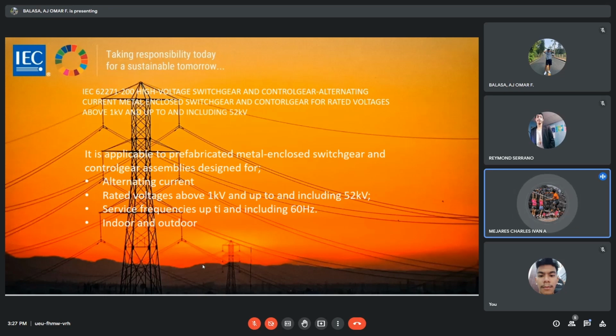IEC 62271-200: High voltage switchgear and control gear, alternating current metal enclosed switchgear and control gear for rated voltages above 1 kilovolt and up to and including 52 kilovolts. It is applicable to prefabricated metal enclosed switchgear and control gear assemblies designed for alternating current, rated voltages above 1 kilovolt and up to and including 52 kilovolts, service frequencies up to and including 60 Hz, indoor and outdoor installations.